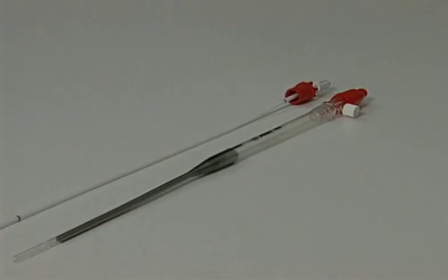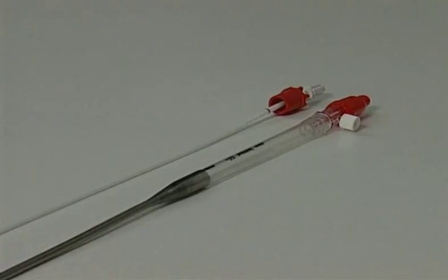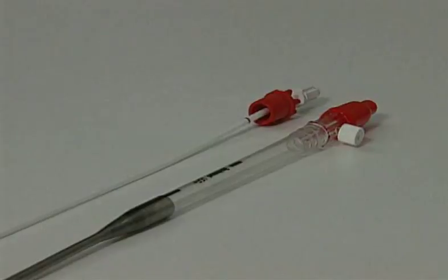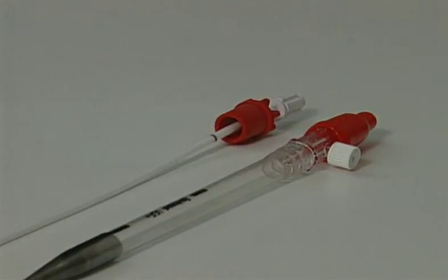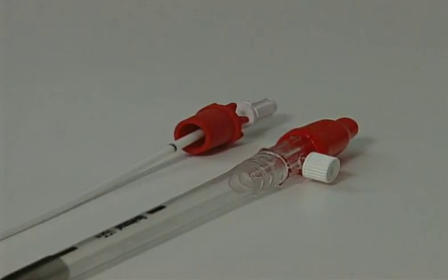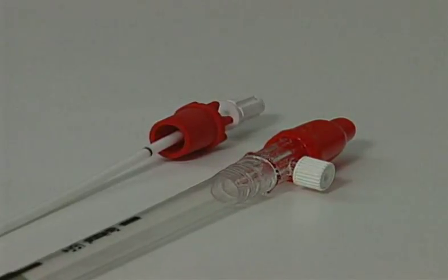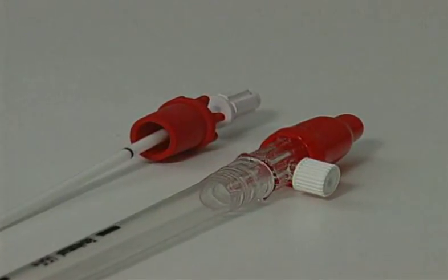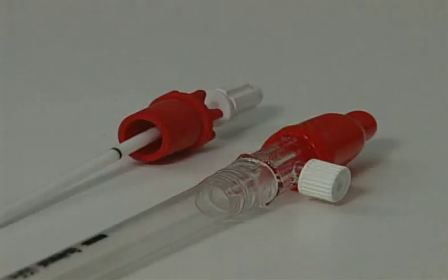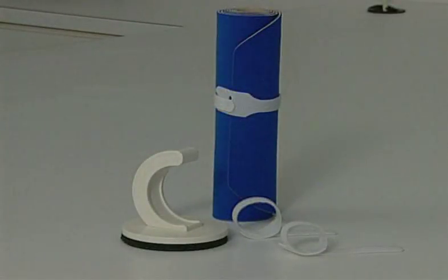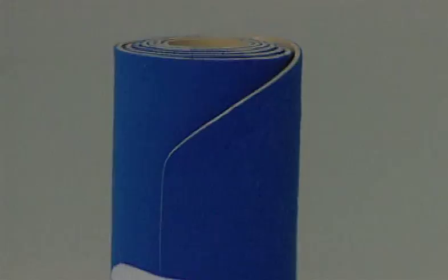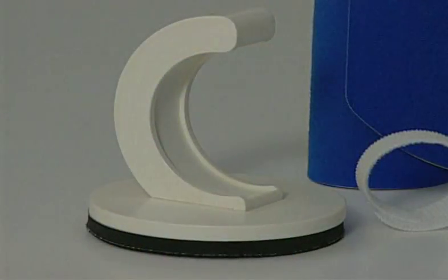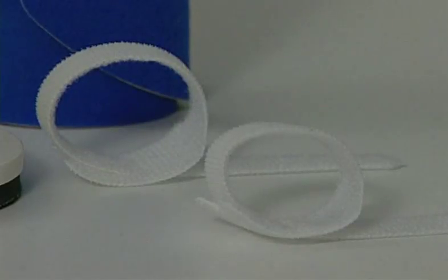Arterial cannulae with 3/8-inch barbed end fitting that offer optimal kink resistance and flow characteristics are recommended. Flow rates of approximately 5.0 liters per minute have been achieved with a 17 French cannula and approximately 4.0 liters per minute with a 15 French cannula. A holster set is used to secure the pump to the patient's leg after support is initiated. This single-use non-sterile set includes a neoprene thigh wrap, C-shaped pump holster, and connector tube tie-downs.